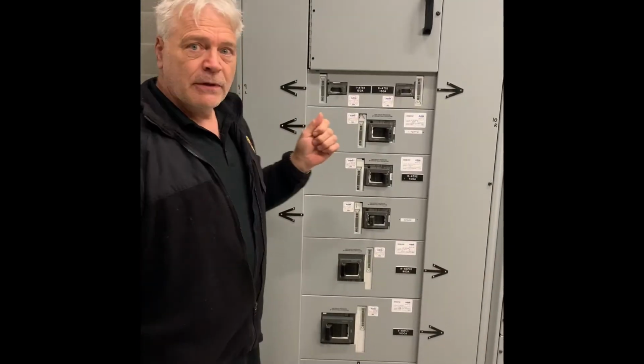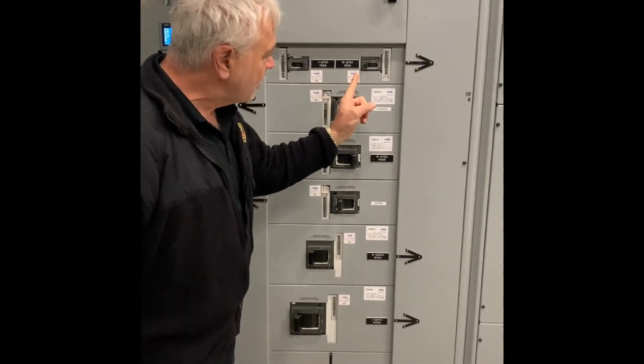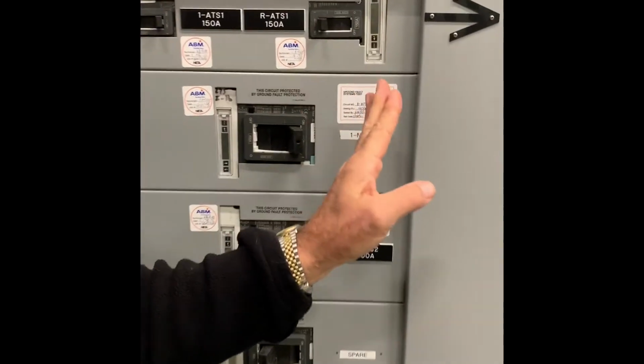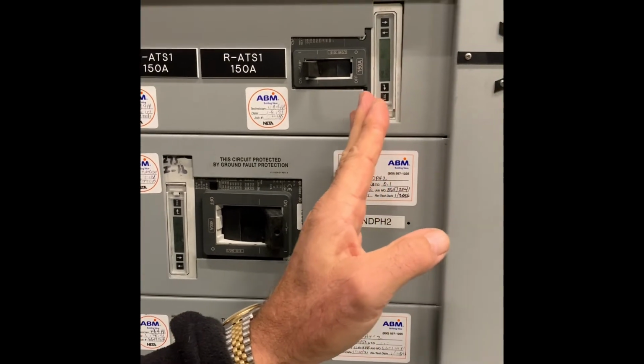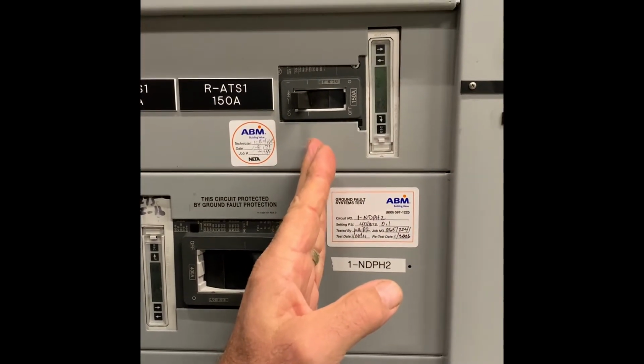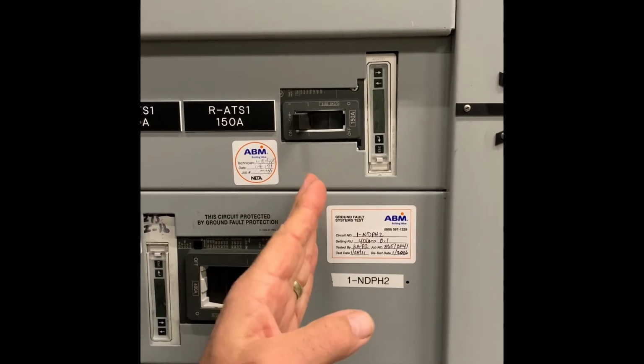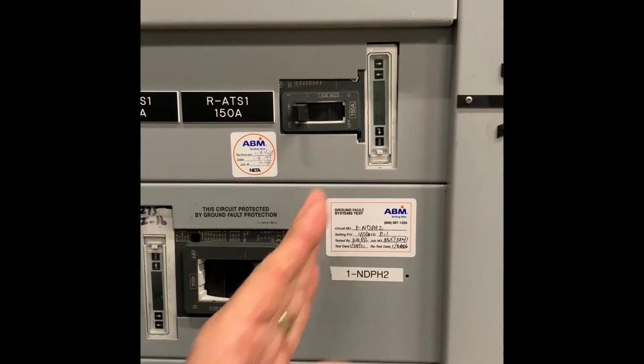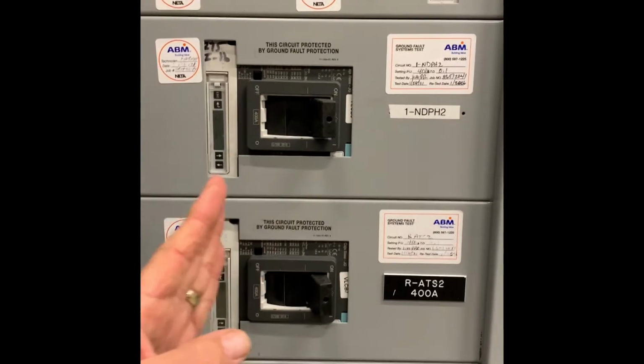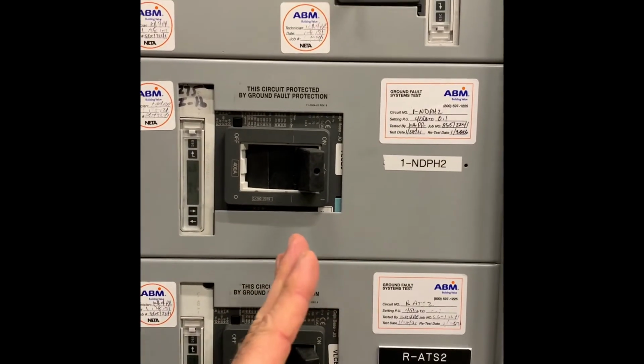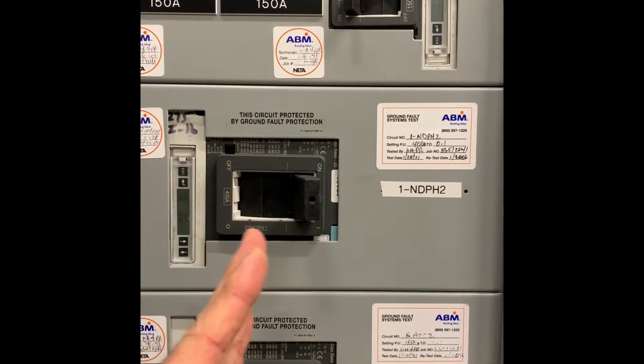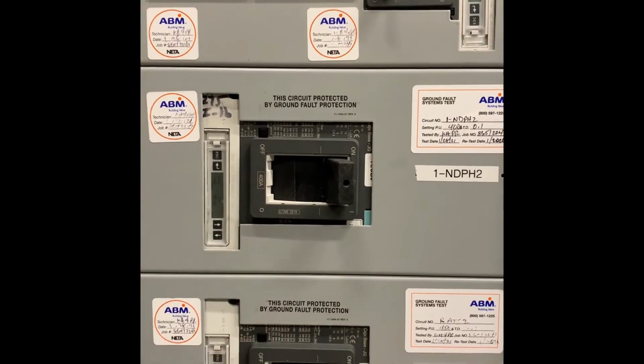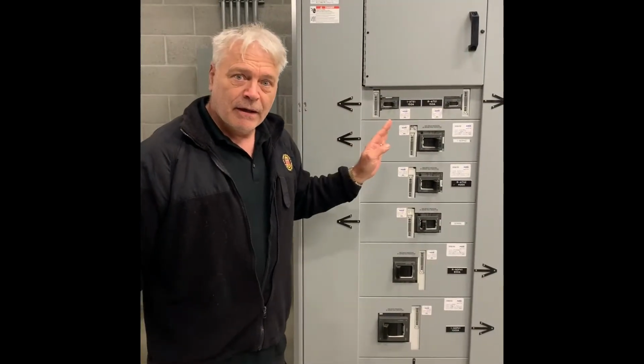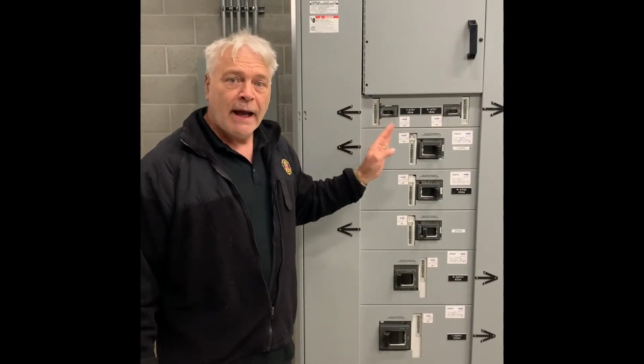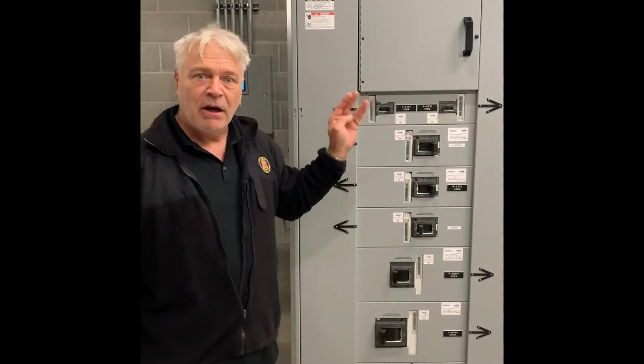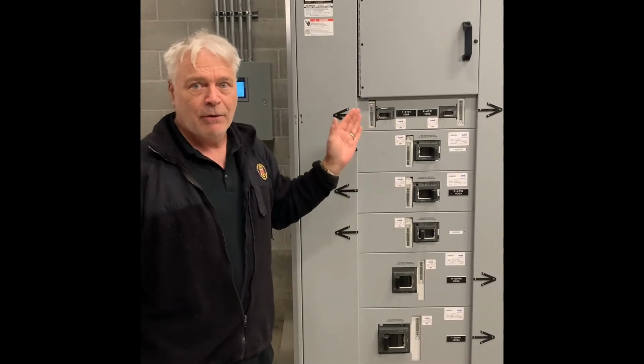I'm briefly going to go over what it looks like if a breaker is tripped. Right now this is shown in the on position. If it was all the way over to this side, it would be in the off position, and right here on this line is tripped. It'll be about halfway. This means that this breaker did its job and opened the circuit. It's the same thing for this larger frame. Off on this side, on this side, and right in the center is tripped. You'll see, it just kind of clicked like that. That's tripped. Do not walk in and reset the breaker until you have identified why it tripped. Once you have identified the cause of the trip, then it can be reset by a qualified person.